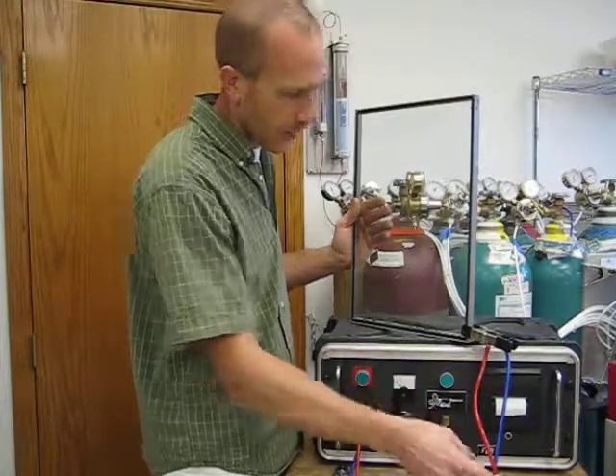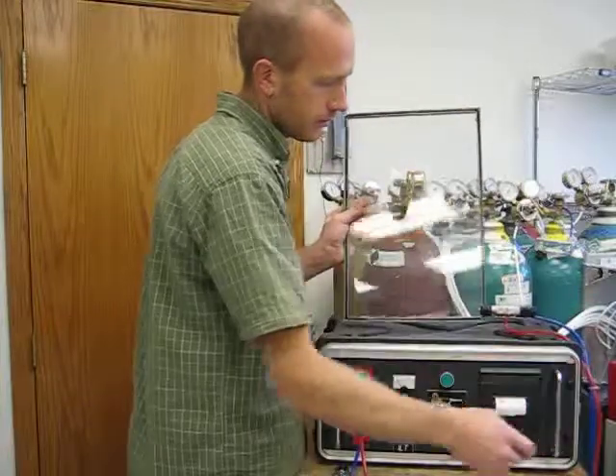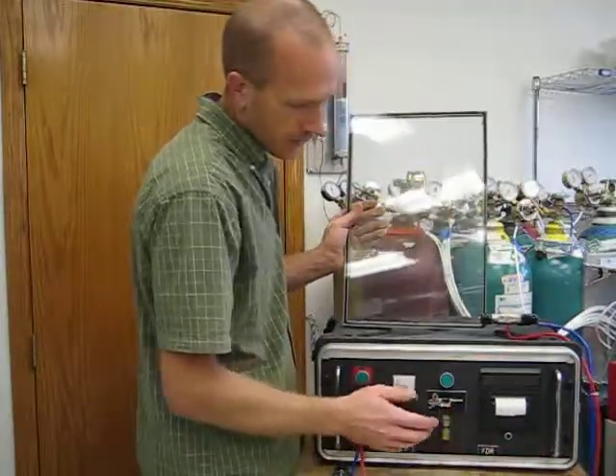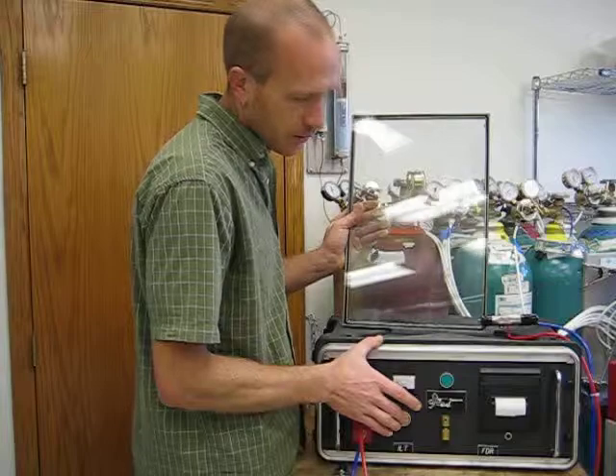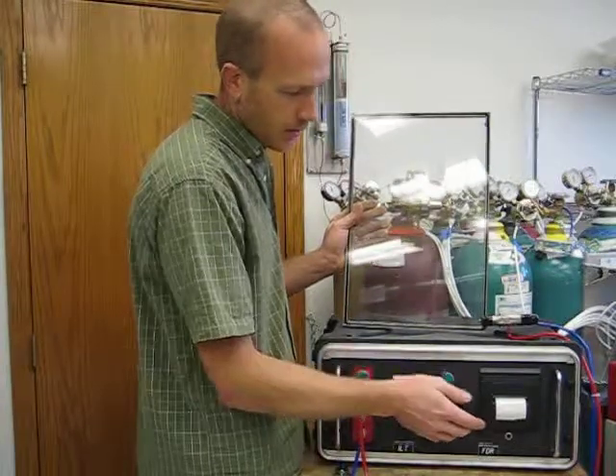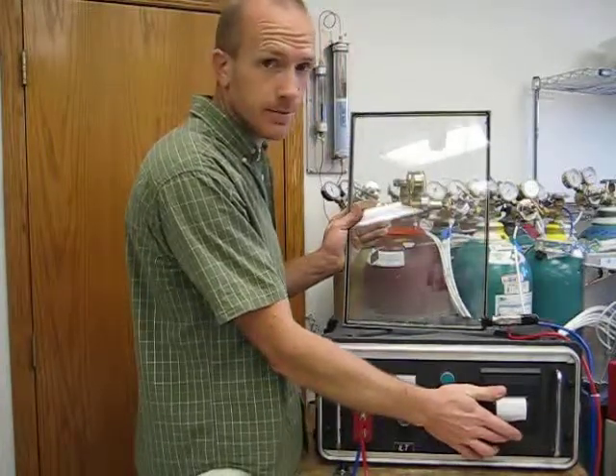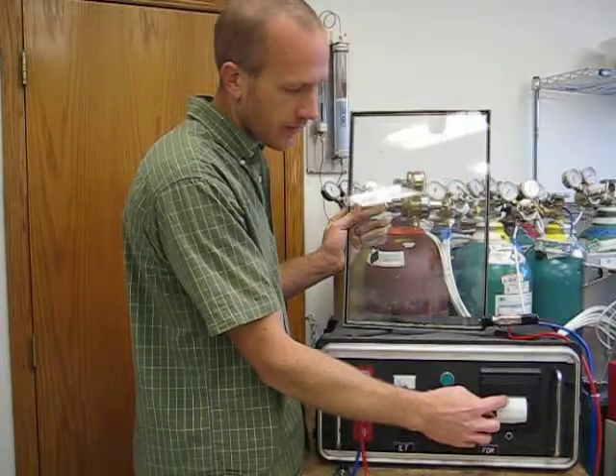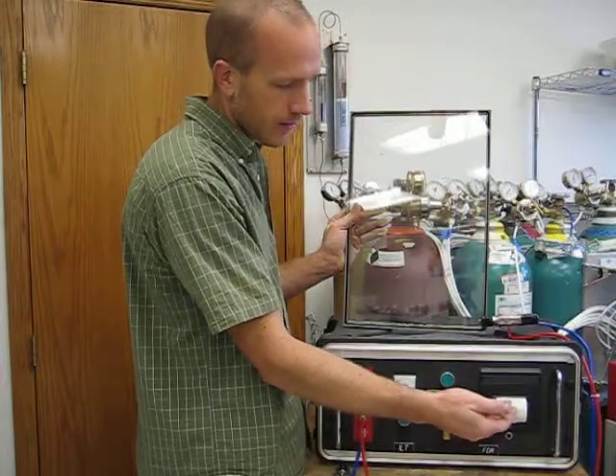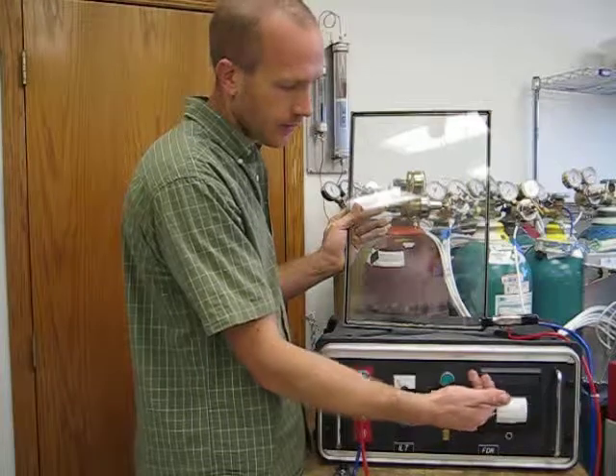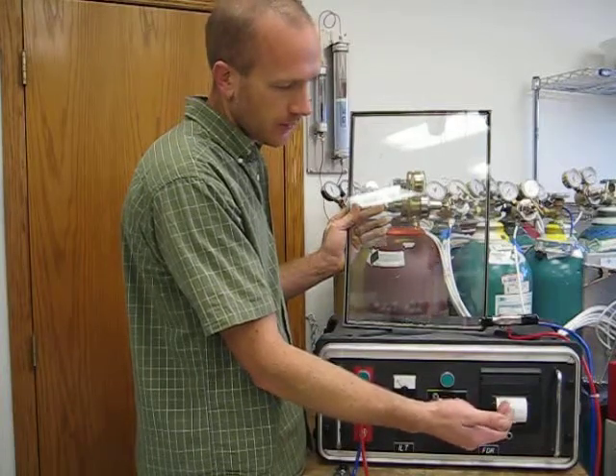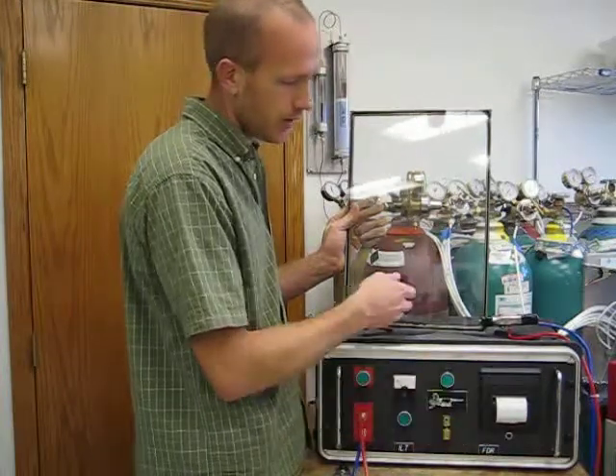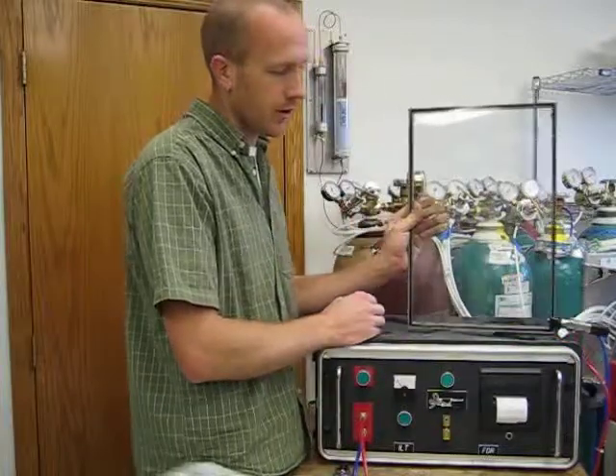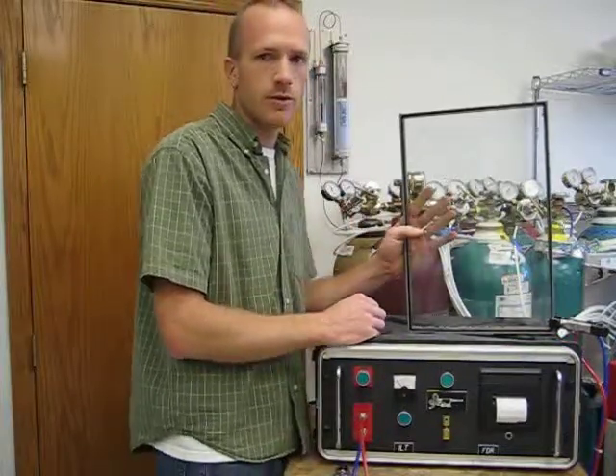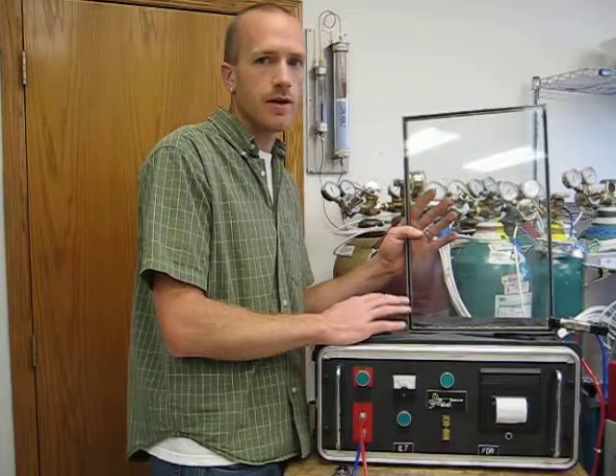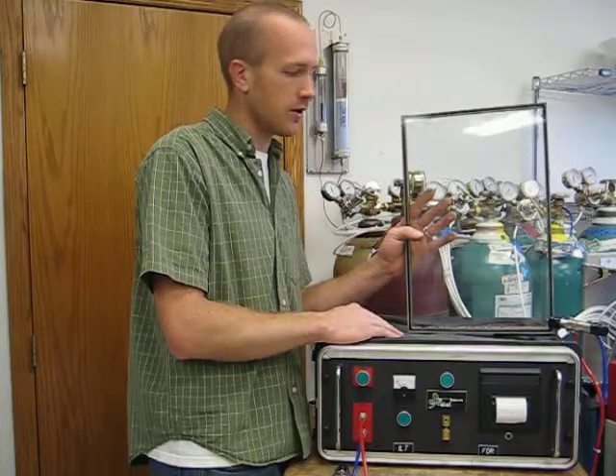This model also has a printer, and you can easily print out a small gas station style receipt that shows the time and the date, and also the serial number of the machine and the gas percentage. And the machine can either be set up for argon or krypton. It's actually measuring the thermal conductivity of that gas. It's not an oxygen analyzer. It's not measuring the oxygen.